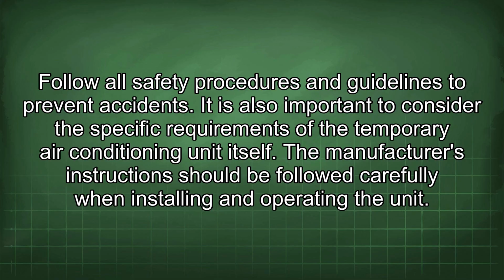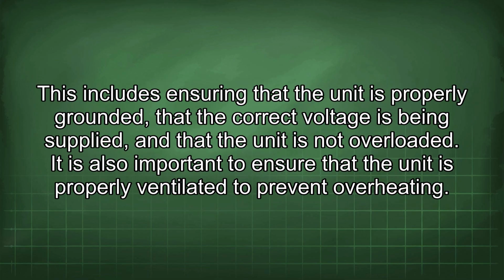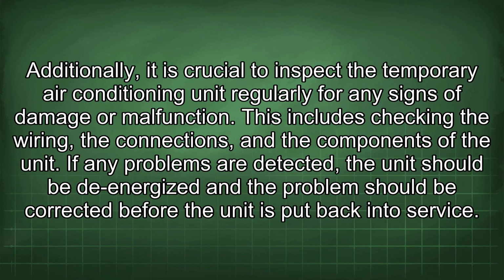It is also important to consider the specific requirements of the temporary air conditioning unit itself. The manufacturer's instructions should be followed carefully when installing and operating the unit. This includes ensuring that the unit is properly grounded, that the correct voltage is being supplied, and that the unit is not overloaded. It is also important to ensure that the unit is properly ventilated to prevent overheating. Additionally, it is crucial to inspect the temporary air conditioning unit regularly for any signs of damage or malfunction. This includes checking the wiring, the connections, and the components of the unit. If any problems are detected, the unit should be de-energized and the problem should be corrected before the unit is put back into service.